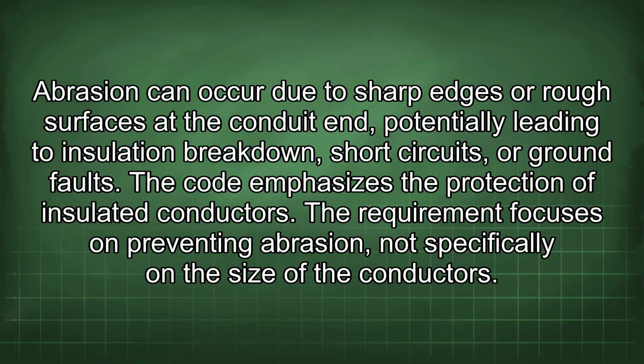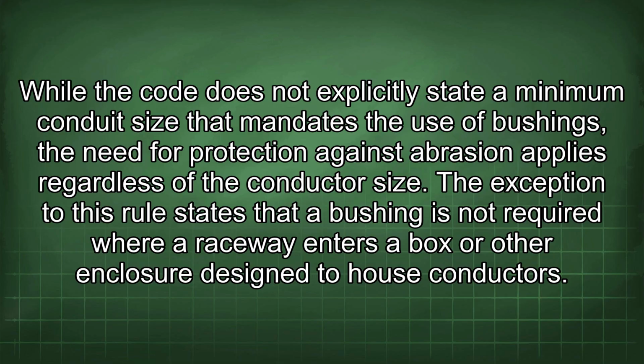The code emphasizes the protection of insulated conductors. The requirement focuses on preventing abrasion, not specifically on the size of the conductors. While the code does not explicitly state a minimum conduit size that mandates the use of bushings, the need for protection against abrasion applies regardless of conductor size.